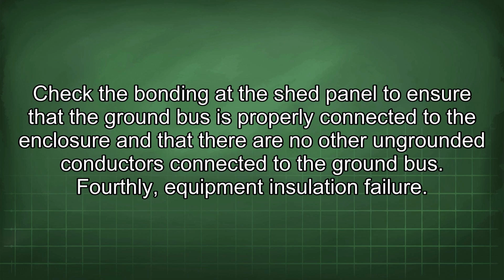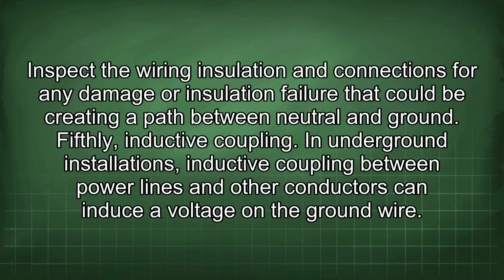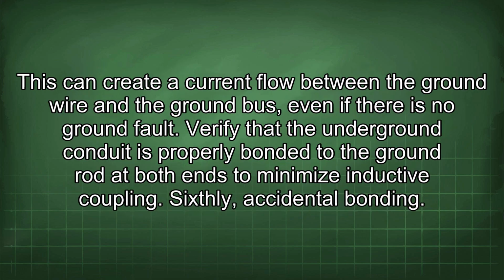Fourthly, equipment insulation failure. Inspect the wiring, insulation, and connections for any damage or insulation failure that could be creating a path between neutral and ground. Fifthly, inductive coupling. In underground installations, inductive coupling between power lines and other conductors can induce a voltage on the ground wire. This can create a current flow between the ground wire and the ground bus, even if there is no ground fault. Verify that the underground conduit is properly bonded to the ground rod at both ends to minimize inductive coupling.